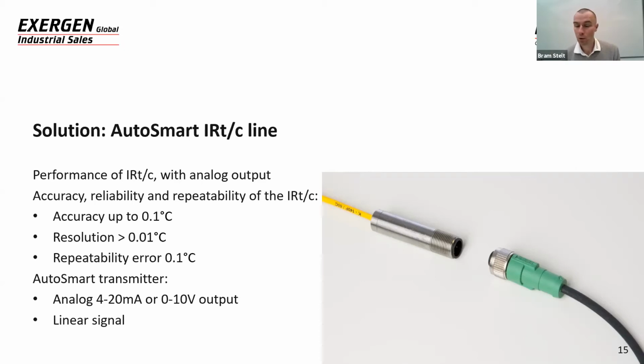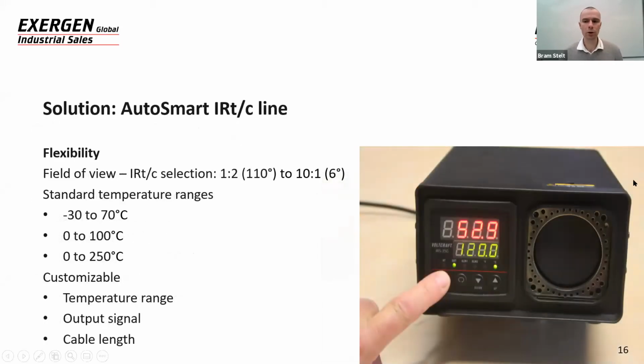However, also to offer the analog output signals, we developed an AutoSmart transmitter where we convert the thermocouple signal of the IRTC into an analog 4 to 20 milliamp or a 0 to 10 volt output. And it's also linearized. So where the IRTC is nonlinear, here the signal is linearized. So it's much easier to use. This gives the performance. We also wanted to give the flexibility that is desired in the market to meet the various demands of the different applications.